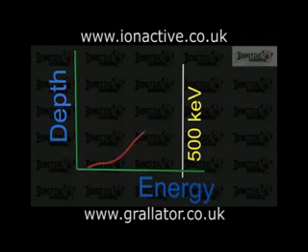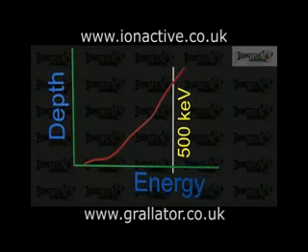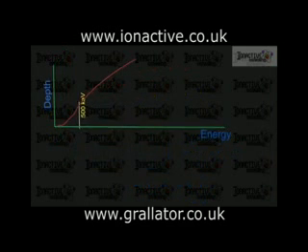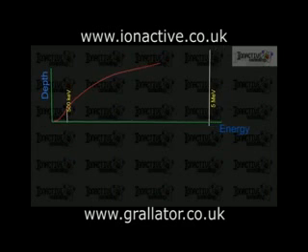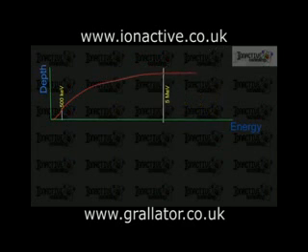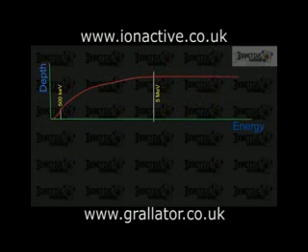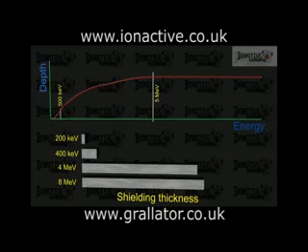Pair production has a significant impact on shielding requirements. It has previously been stated that as the photon energy increases, so does the penetration depth into a material. However, for sufficiently high energy photons, above about 5 MeV for lead, pair production becomes dominant. This effectively reduces incident photon energy to no more than 511 keV at the first scattering event, instead of allowing for a more continuous spectrum of scattered energies as seen with Compton scattering. Therefore, while thicker shielding is required for these higher energies, the fractional increase required is not as large as that seen for lower energy photons.